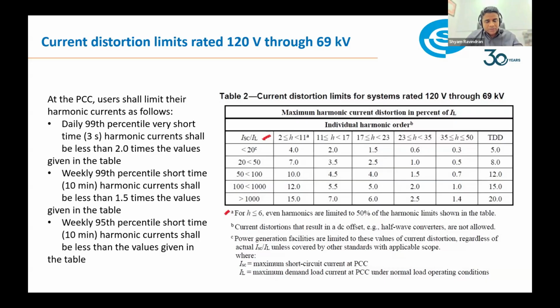And we derive what the ISC by IL value is. Let's say your ISC by IL value is somewhere between 20 to 50. Then your total TDD allowed limit is 8. Please read on the left-hand side: the 99th percentile, very short time, harmonic current shall be less than 2 times the values. It's actually the 99th percentile, not the percentage of the value.